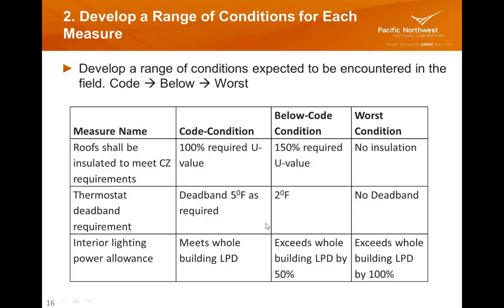Thermostat deadband is a requirement that says there needs to be an offset between the heating and cooling set points on a thermostat. The code condition is a 5-degree deadband. Below code condition we identified was 2 degrees, and the worst case was no deadband at all.